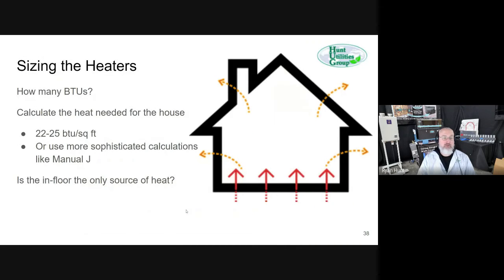We'll talk about the heater selection. How do you choose which heater you need? It basically comes down to fuel type and size. We'll talk about size here, which is rated in BTUs, and the electric ones are rated in kilowatts, which converts to BTUs. And we can help you size that out. But the size of boiler you need, the number of BTUs, depends on how your house or building is built. How much does it take to heat that building? That's a function of the shell, the amount of insulation in the walls and the roof, how airtight it is, and how many windows there are. Windows are about R3 compared to a typical wall, which is R25 to 30, or upwards of 30 in more high performance buildings.